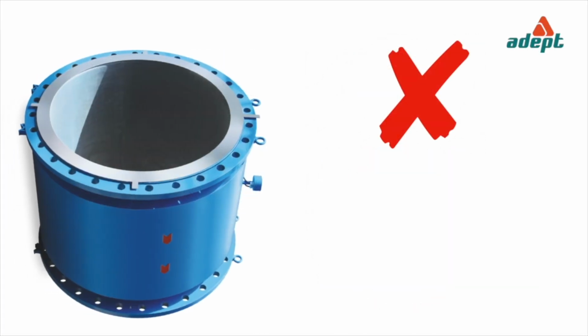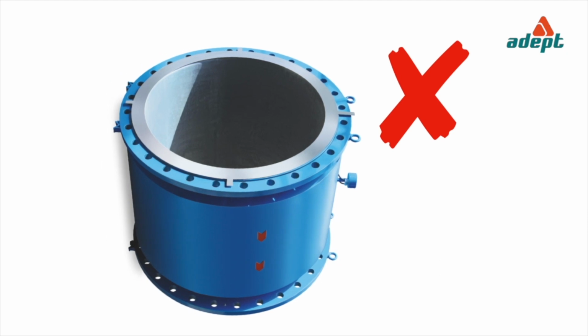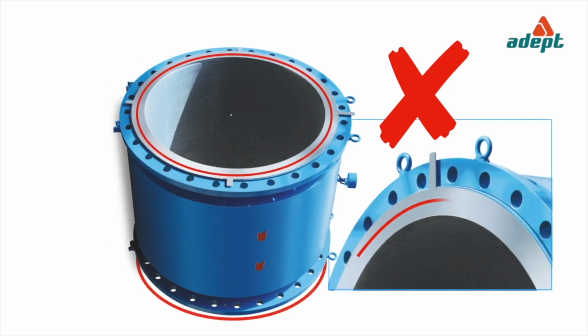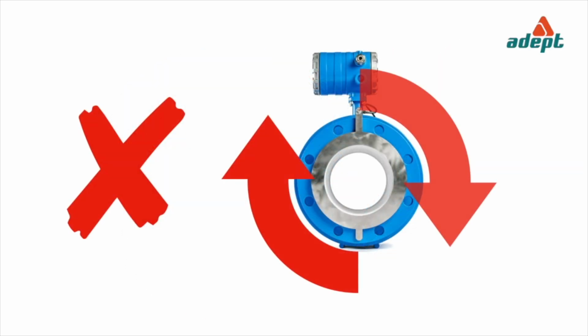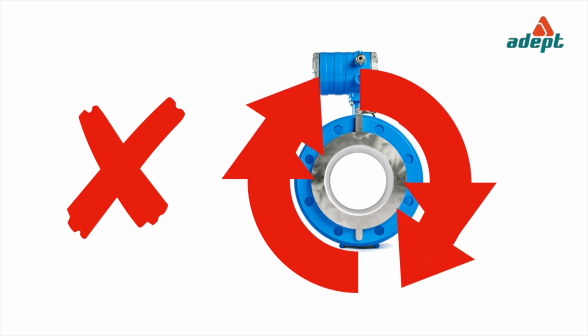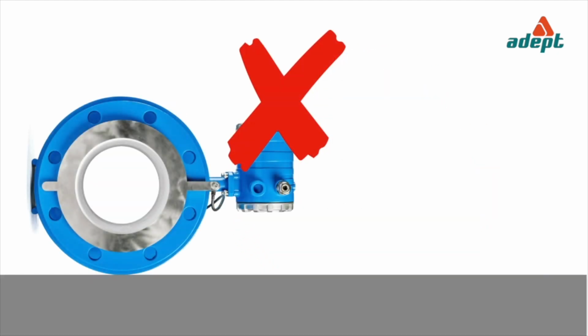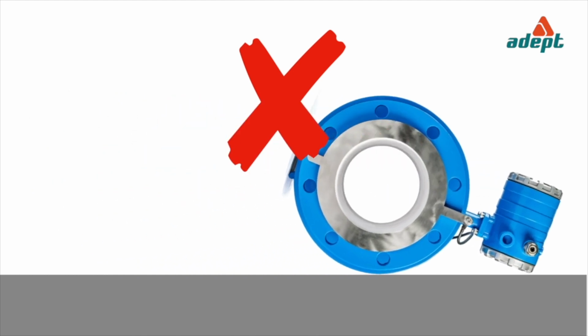Do not drag the flow tube with its lining facing the ground. This will damage the lining. Do not roll the flow tube over its flanges. This will damage the flanges and also the transmitter or the junction box if it hits the ground on rolling.